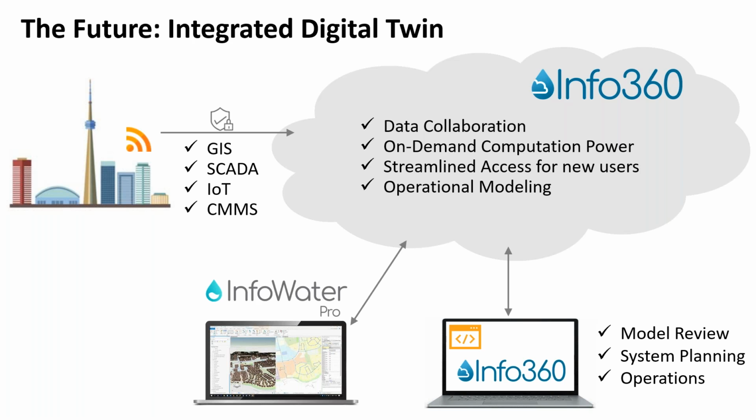I don't have my Info360 up and open, but within the mass balance that Hunter showed, there is an area for the billing data. If you have a time series of billed AMI data, we calculate the total water usage, and you can subtract out what is billed to directly give you a time series of your non-revenue water. That can then be used for alerts and dashboards.